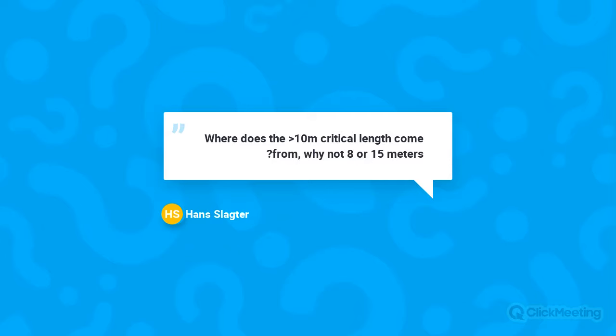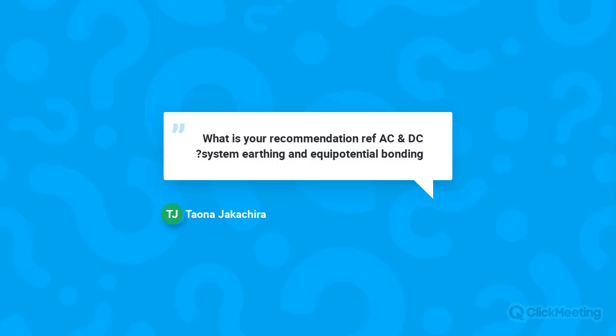Okay, what is your recommendation for AC and DC system earthing and equipotential bonding? So the recommendation again for the earthing system is the 20 by 20 or the 40 by 40 mesh. We do find ways around it in terms of simulations, but you have to prove that it will still be sufficient. The equipotential bonding stays with the 6 millimeter and the 16 millimeter rule for direct and indirect lightning currents. But those are all highlighted specifically in the lightning protection standard. If you need us to look at that for you, please just send us an email through and we can assist you with that as well.